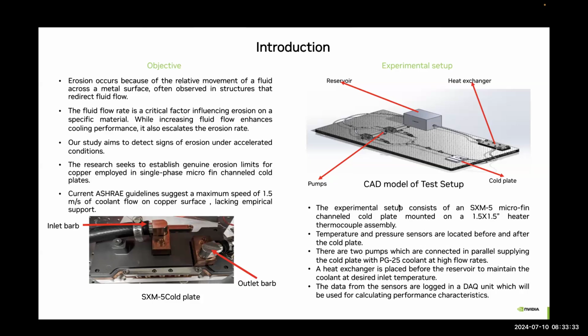The second thing we looked into is that we used two cold plates at the same time, since you can't open a cold plate. One is a completely new manufactured cold plate that was never used. After running the test for five months, we cut the used cold plate open, took all the images, and compared both cold plates, without use and with five months of testing.